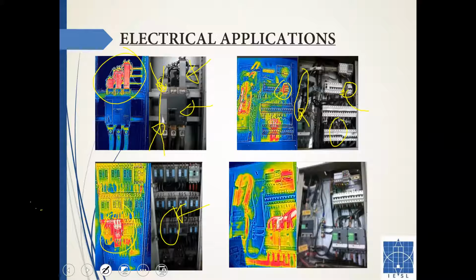If you pay close attention here, you have a bad connection because you see a red hotspot right there, and there are some tiny details you can miss. So your thermographer must be skillful enough to identify those, and attention to detail should be really critical. It's crazy - you miss one thing and that could cause a fire. So attention to detail is really important. Take things slow, take your time, and check your work. That's one thing I learned.